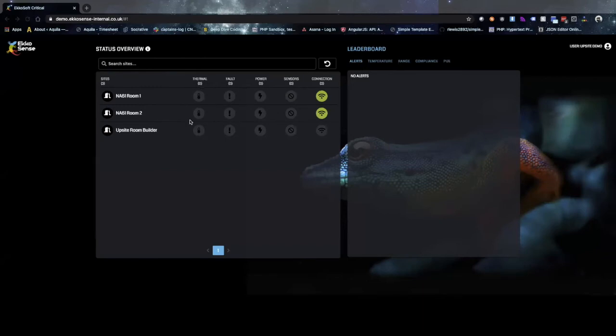Then what you'll get next is the alerts. So thermal alerts if something's too hot or too cold. Faults, which are actually configurable by the end user. So for example, if someone has leak detection equipment that they want to port into the software for alerting, that will appear here. Next is power alerts. So if there's a spike or a drop in power, for example. And then the last two are connectivity. So sensors, if we lose connection to a sensor or the batteries are low, we'll get an alert here. And then actual connection to the cloud, just so we can make sure everyone's up and running and talking to EkkoSoft Critical.